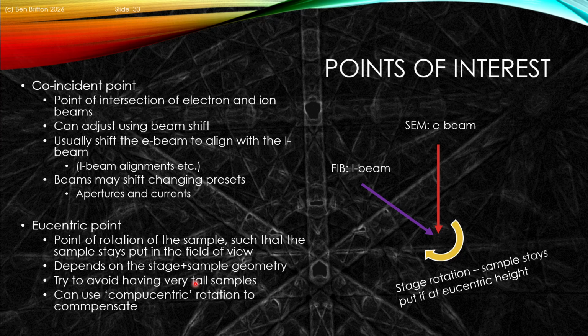Another important aspect of the instrument, especially for our dual beam system, is the availability of the so-called coincident point. Typically, because the FIB is interacting heavily with your surface, you don't want to spend too much time imaging the surface of your object using the FIB, because you can get ion beam damage, sputtering and removal, etc. Furthermore, you're going to use the fact that you have two beams to enable you to get a sort of three-dimensional picture of your object, and we'll see that's important for things like lift-out operations.